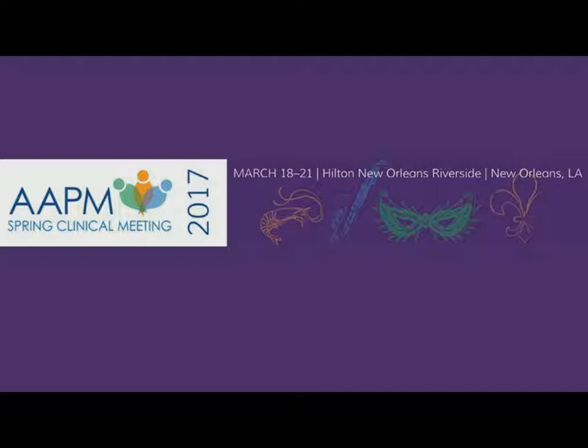Melissa, thank you for a wonderful talk. One of the things that didn't come out, which I think is becoming increasingly a problem, is the size of the room. Typically, to get all of the functionalities of a modern-day linear accelerator, there's a minimum size that you require because of all the imaging and the camera systems that we have. And the vendors will sell you any machine to go into any room. So are there any recommendations, or is anybody looking at what the minimum vault size is to get complete functionality of a linear accelerator? The vendors will give you the minimum.